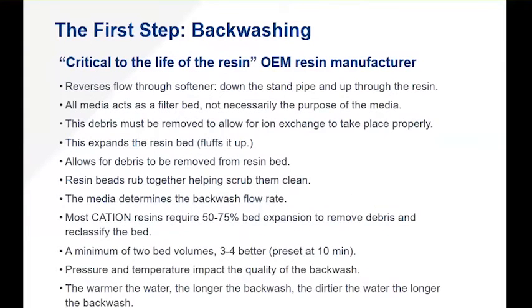The first step is backwashing. To quote an OEM of resins in the marketplace, this is critical to the life and performance of the resin in the tank — it's the most important step. Why would a resin manufacturer stress backwashing? What happens during backwashing is we reverse the flow through the softener. The piston moves in or the flappers move inside the valve, reversing flow and opening a waste line. The water goes down through the center standpipe, out the distributor, up through the resin and out to waste.